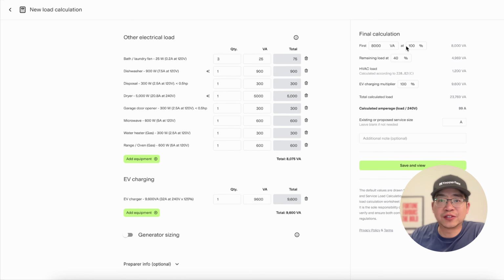To finish off the load calculation, we now get to apply a load reduction from 220.83. It can be tricky since the code requires that the first 10,000 VA are taken at 100% for new construction, but only the first 8,000 VA at 100% for retrofits like this one. Then you get to apply the 40% beyond that. We've seen this trip people up. Fortunately, the calculator handles this for you automatically based on the dwelling condition that you select.